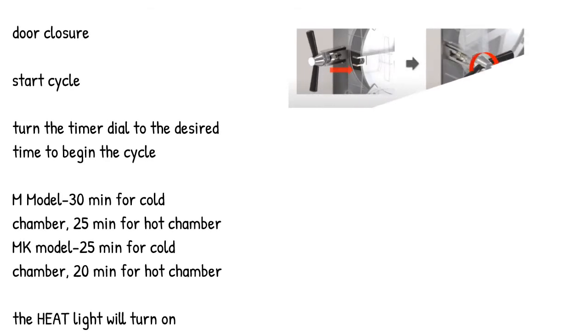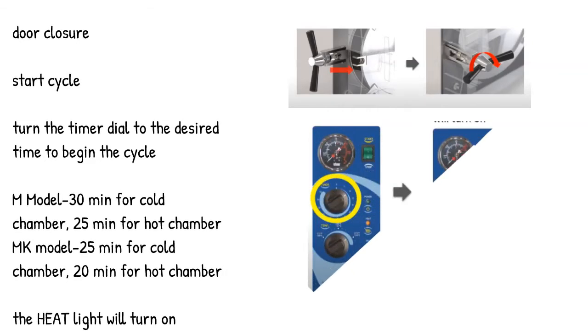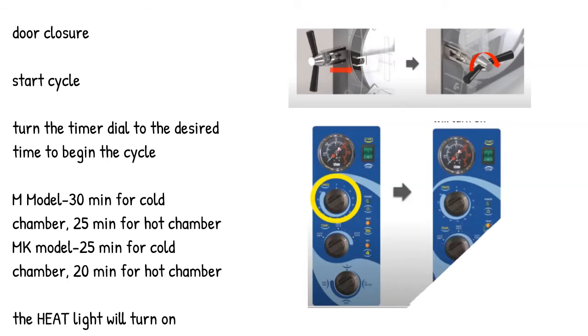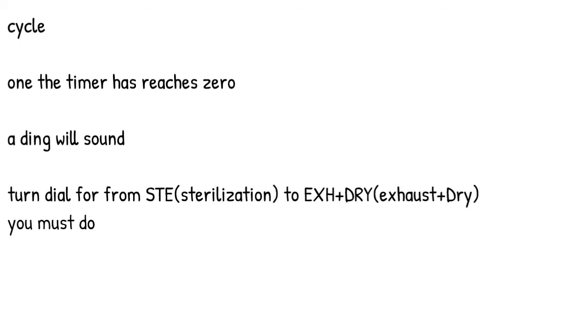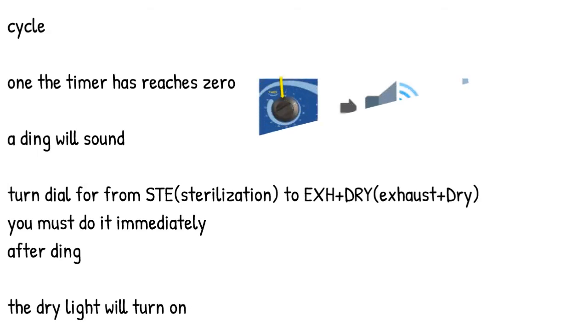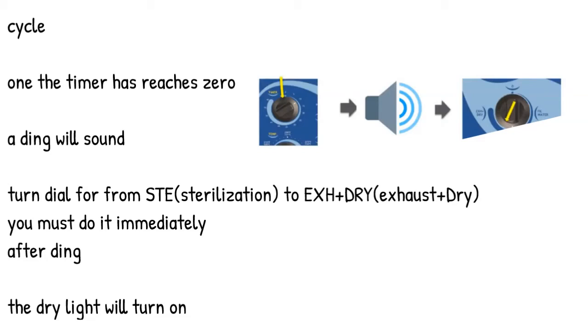Door closure. Start cycle. Turn the timer dial to the desired time to begin the cycle. M model: 30 minutes for a cold chamber, 25 minutes for a hot chamber. MK model: 25 minutes for a cold chamber, 20 minutes for a hot chamber. The heat light will turn on. Cycle: when the timer reaches 0, a ding will sound. Turn the dial from STE, sterilization, to EXH plus dry, exhaust plus dry. You must do it immediately after the ding. The dry light will turn on.